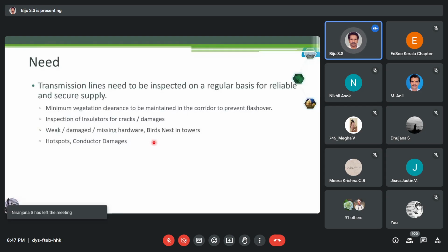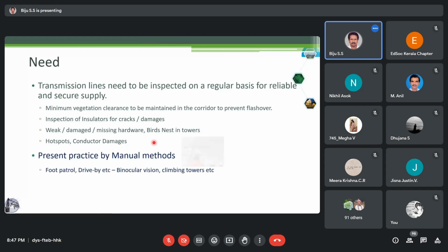The need, why it is required. Transmission lines need to be inspected on a regular basis for reliable and secure supply. Minimum vegetation clearances have to be maintained. Inspection of insulators for cracks and damage has to be done. Weak, damaged, or missing hardware has to be identified, and bird nests have to be removed. Hotspots or conductor damage have to be detected. These are all the things necessary during a line inspection.